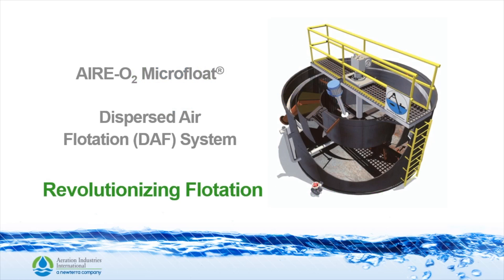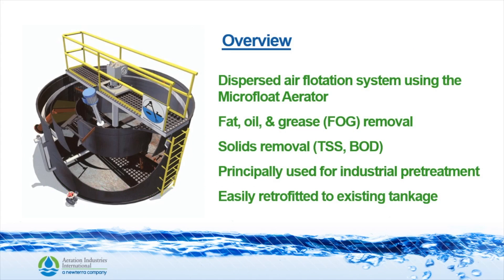Our AIRE-O2 Microfloat unit is a dispersed air flotation system, compared to a dissolved air flotation system. The microfloat unit uses micro-bubbles to remove fats, oil, and greases (FOG), as well as suspended solids and BOD. Its principal use is industrial pre-treatment and it is easily retrofitted into existing DAF tanks.